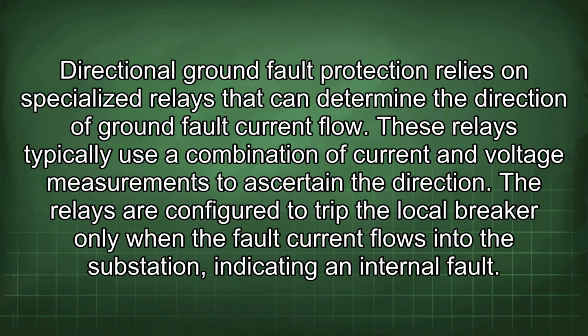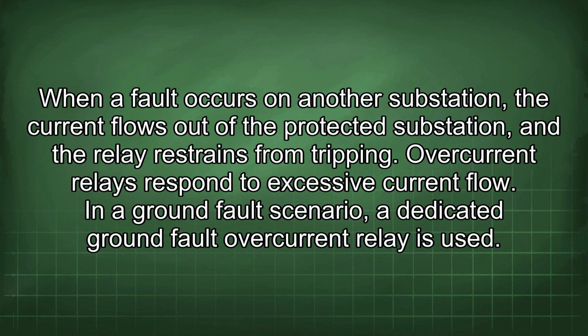Directional ground fault protection relies on specialized relays that can determine the direction of ground fault current flow. These relays typically use a combination of current and voltage measurements to ascertain the direction. The relays are configured to trip the local breaker only when the fault current flows into the substation, indicating an internal fault. When a fault occurs on another substation, the current flows out of the protected substation and the relay restrains from tripping.